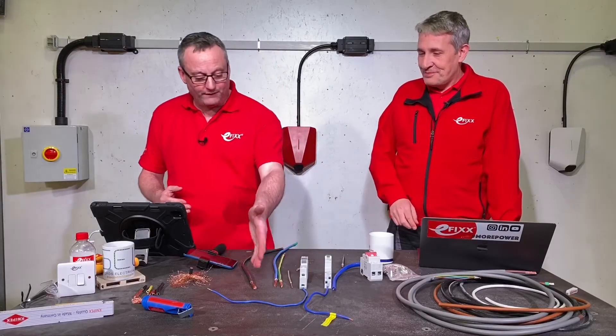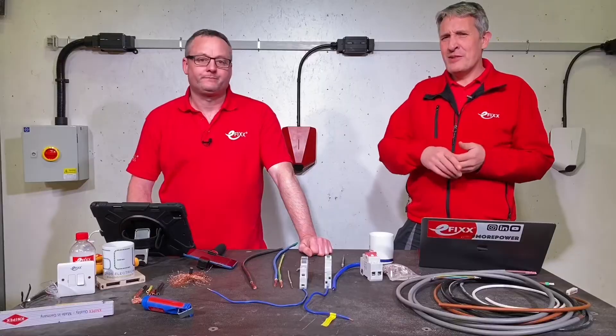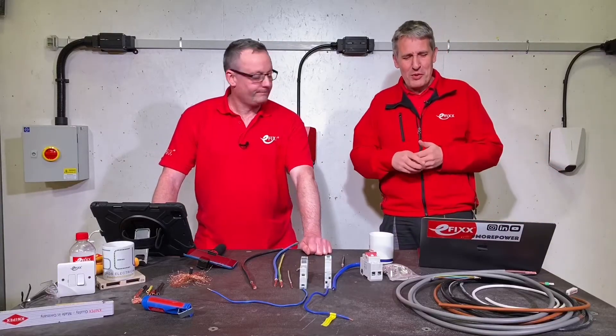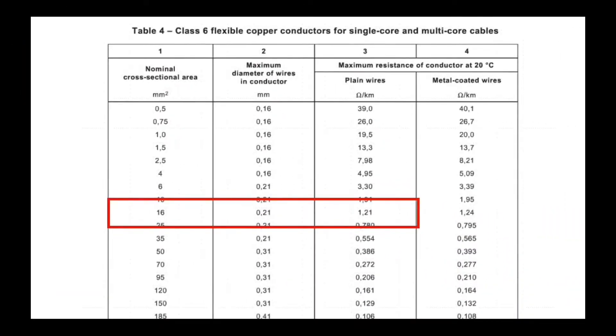We did a video a while ago that looked at fake and substandard cables — someone had short-changed the customer and the copper in there was reduced, so there weren't as many strands as expected. With 504 strands to go at, if you missed 10 out would anyone really know? The way to check is the resistance of the cable, because that is defined in the standard. A 16mm cable's maximum resistance should not be more than 1.2 ohms per kilometre for a class 5 or class 6 conductor.